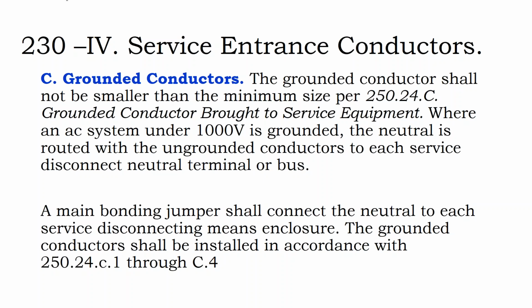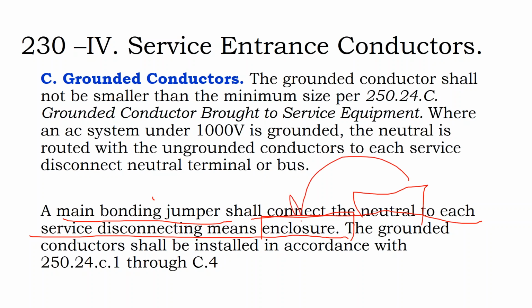We see in 230, a main bonding jumper shall connect the neutral to each service disconnecting means enclosure. Yeah, this is where your neutral is being bonded to your system ground. If your service disconnecting means enclosure is connected to your grounding system and your neutral is being bonded to that grounding system, there's actually one point in your system where you're taking your neutral wire and taking a piece of metal and touching it to ground and leaving it like that.